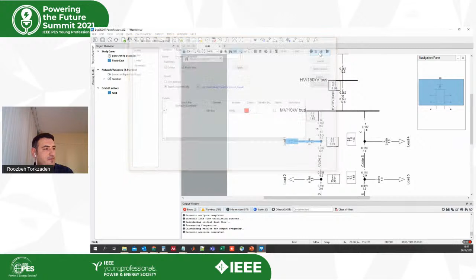It will ask you for which elements you want to see the result. Yeah, for example, in this case, I want to see the result for the 10 kV bus bar. And for which variable I want to see the harmonic distortion. And when you press OK, you can see this nice curve here. So let me do this. So you can see that for the first harmonic, we have the magnitude of 100%. And for the other harmonics, it's not that much.